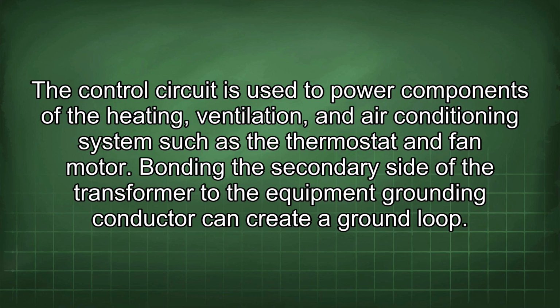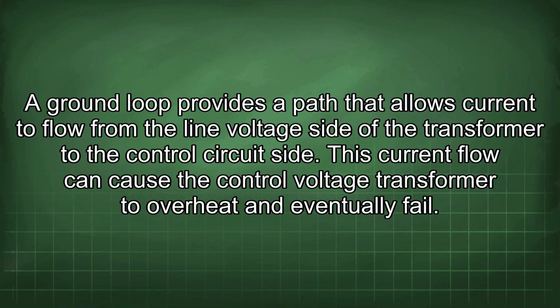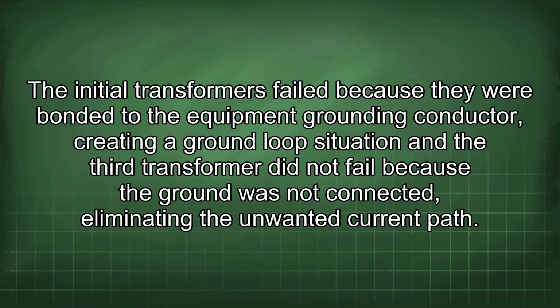and fan motor. Bonding the secondary side of the transformer to the equipment grounding conductor can create a ground loop. A ground loop provides a path that allows current to flow from the line voltage side of the transformer to the control circuit side. This current flow can cause the control voltage transformer to overheat and eventually fail. The initial transformers failed because they were bonded to the equipment grounding conductor, creating a ground loop situation, and the third transformer did not fail because the ground was not connected, eliminating the unwanted current path.